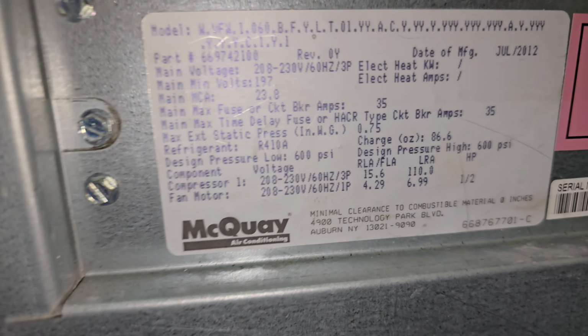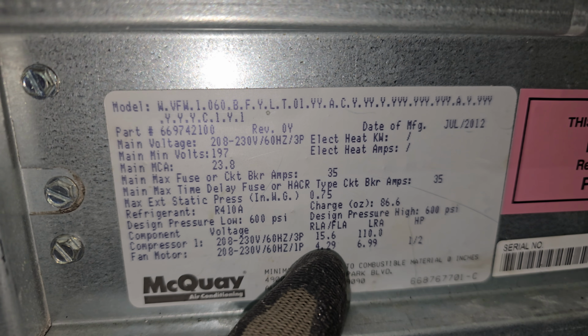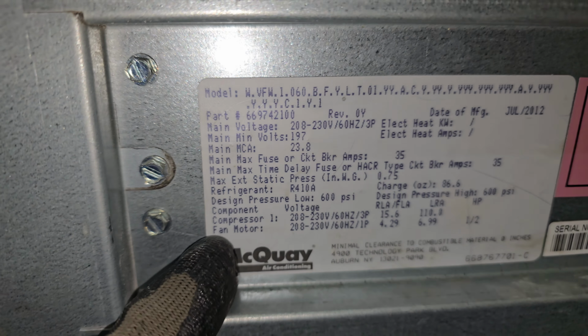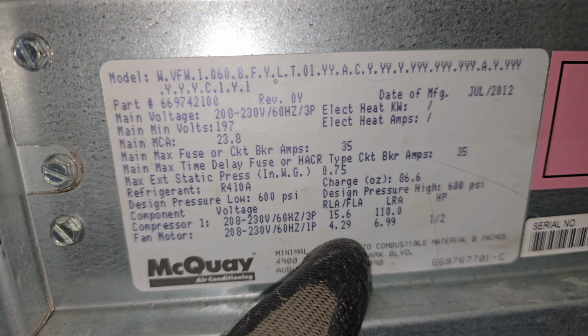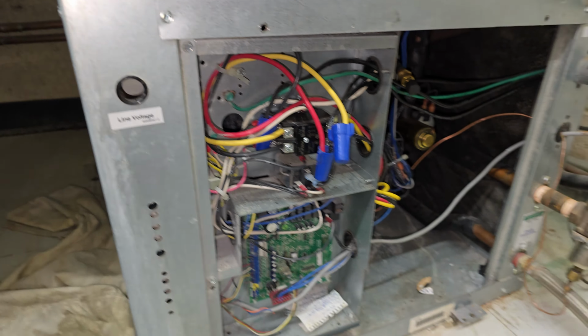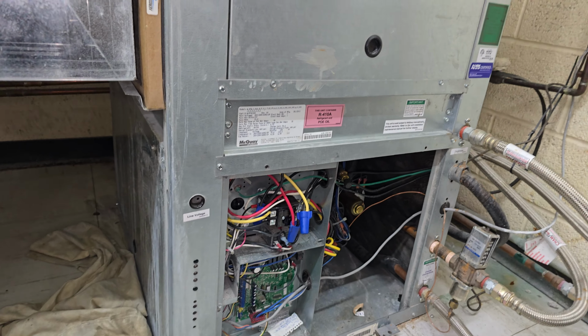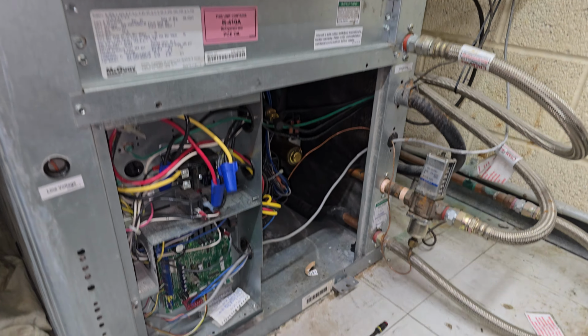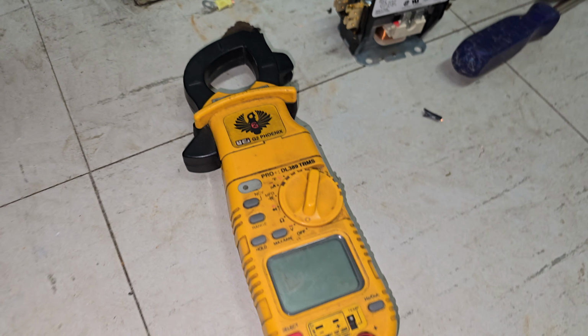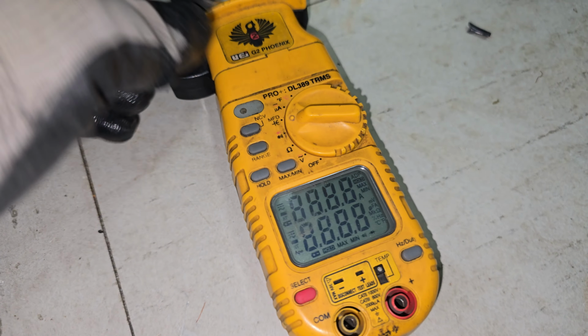So you can see here, my compressor amps reading said 15.6, and my fan motor amps reading is 4.29 to 6.99. Okay, so I'm gonna take my amps reading, and I'm gonna set my meter to amps reading, so I could take the amps reading. Okay, so my amp meter is set now.